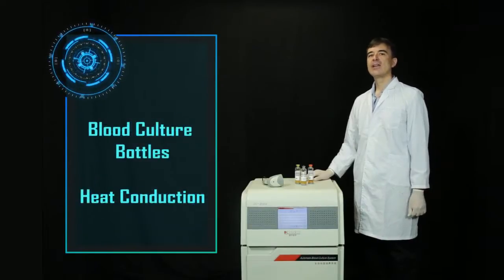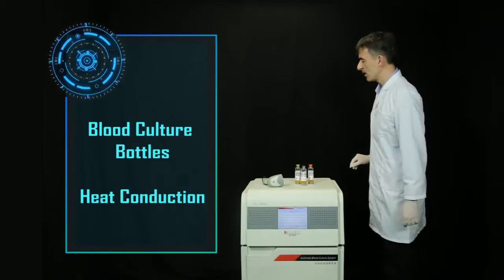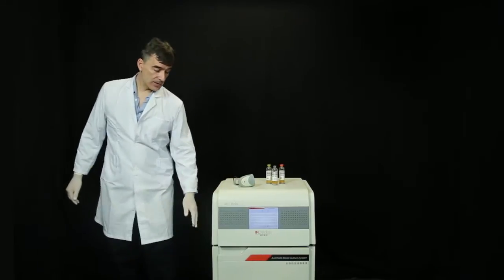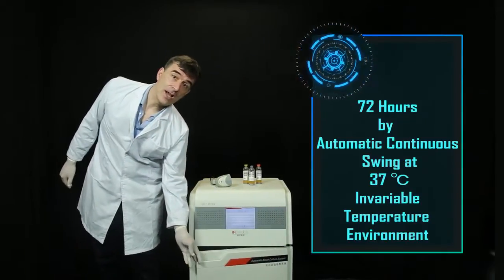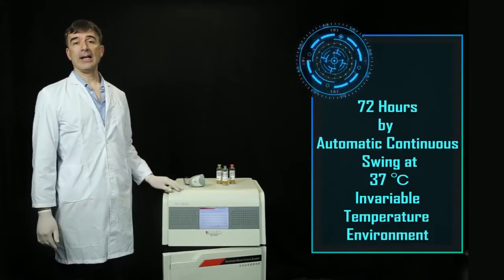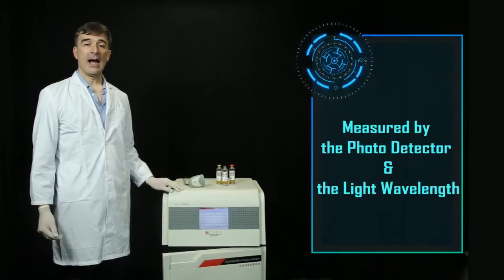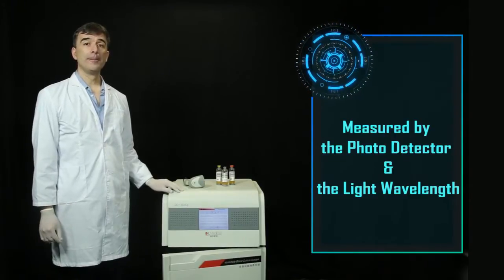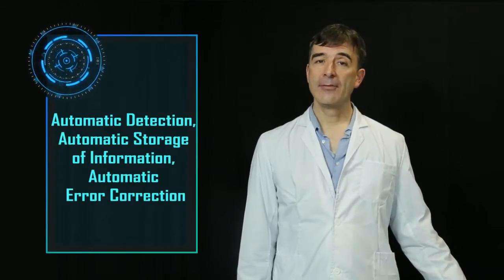Put inoculated blood culture bottles into the rack. Using the principle of heat conduction, blood culture bottles can be incubated for 72 hours by automatic continuous swing at 37 degrees Celsius in an invariable temperature environment. This makes microorganisms rapidly grow in the bottle. The bottles are measured by the photodetector and light wavelength using a variety of mathematical models and statistical analysis to produce accurate results of microbial growth.